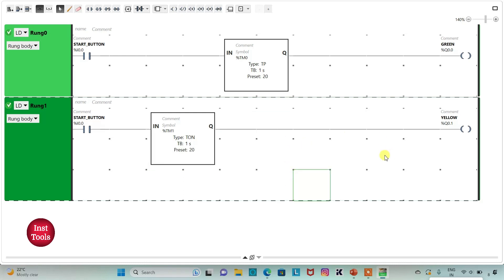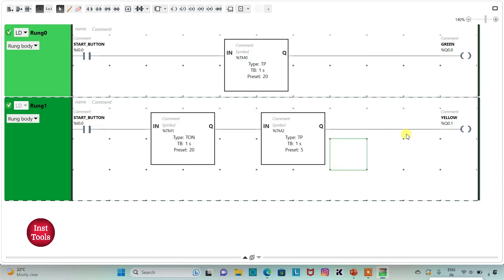There should be a delay of 20 seconds, so I will insert a TON timer with time base as one second and preset value as 20, then click Apply. The yellow light should be on for 5 seconds, so I will insert another TP timer with time base as one second and preset value as 5. Yellow will turn on after 20 seconds and stay on for 5 seconds.